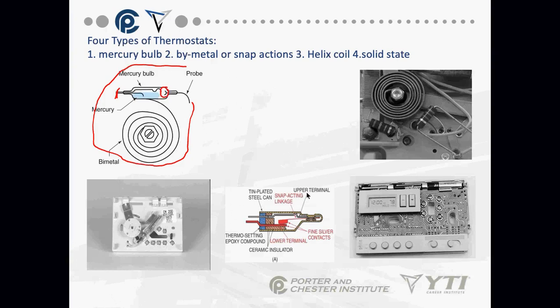Okay, the snap action is down here. Again, there's a piece of bimetal. By bimetal we mean two different types of metals that have been sandwiched together. They expand and contract at different rates, so as it heats up and cools, it actually changes shape. And as the thermostat heats and cools, this little action in the center here will switch positions and will snap together and close or open circuits. So again, the bimetal snap action is right there.